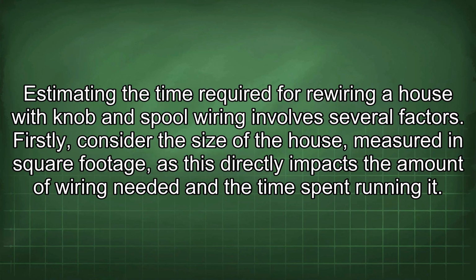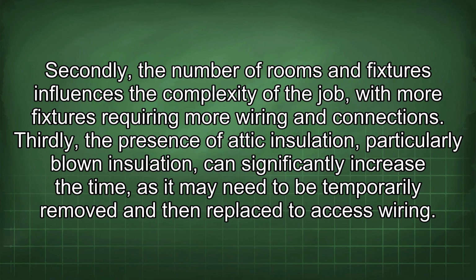Estimating the time required for rewiring a house with knob and spool wiring involves several factors. Firstly, consider the size of the house, measured in square footage, as this directly impacts the amount of wiring needed and the time spent running it. Secondly, the number of rooms and fixtures influences the complexity of the job, with more fixtures requiring more wiring and connections. Thirdly, the presence of attic insulation, particularly blown insulation, can significantly increase the time, as it may need to be temporarily removed and then replaced to access wiring.